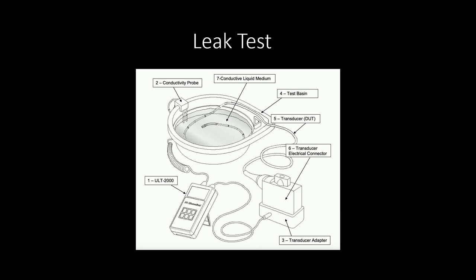So you can see the probe is in, and it's ridiculously easy. They throw it in a bucket of water, basically. Number two there, the conductivity probe, is just like two electrodes that sit in the water. It electrifies the water. And then they have this specialized meter that's connected to that, and it's also connected to the head of the probe, or the head of the transducer. And that little machine just says failed, didn't fail.